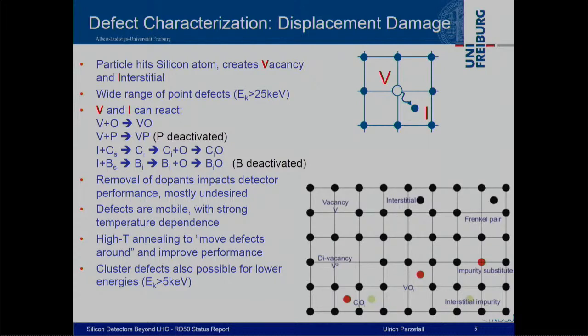And in these cases, you can see that the dopants that you originally had get deactivated, and this will have an impact on your detector performance, which in almost all cases is something undesired. I should also point out that these defects are mobile with a very strong temperature dependence. So the warmer you have your detector, the more these defects move around, and this is something we call annealing. And that can, and you'll see later some examples of this, be used to improve your detector performance.